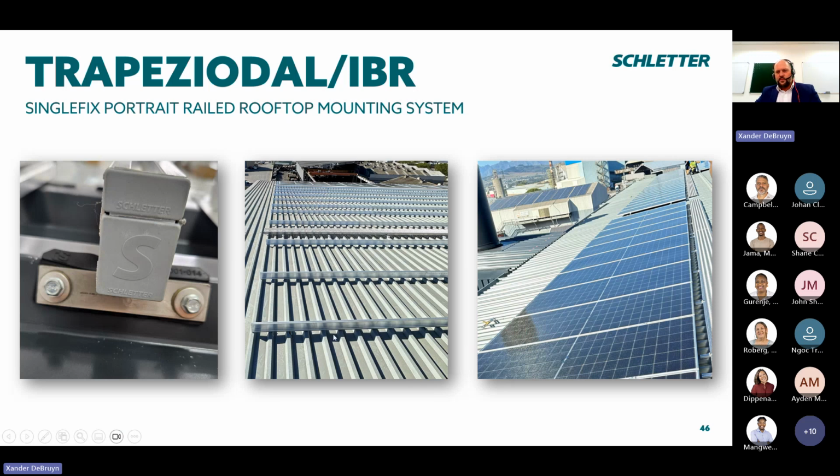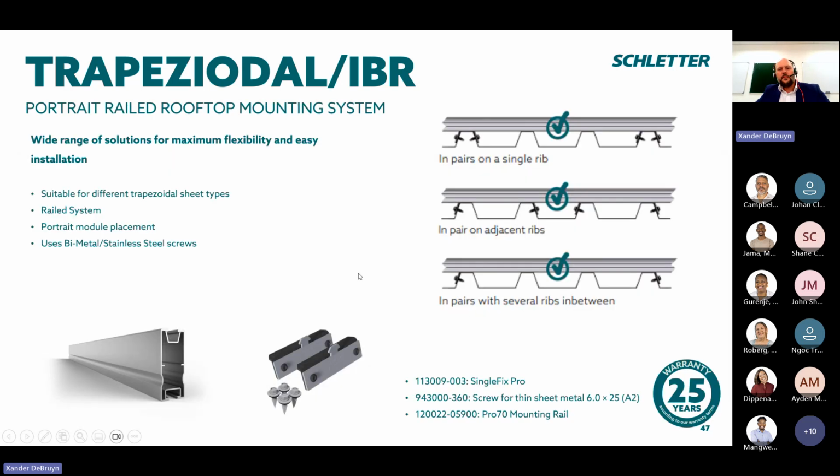So IBR is pretty straightforward compared to the concealed fix. And you'll notice that we're using quite thick rails here compared to our other systems. This is for that ventilation gap that we were talking about earlier, so that the modules have high clearance over the rooftop. It has a second added benefit that high rails are also strong rails, so you can span pretty far in many scenarios using less screws and fixings, which also saves you time on site.